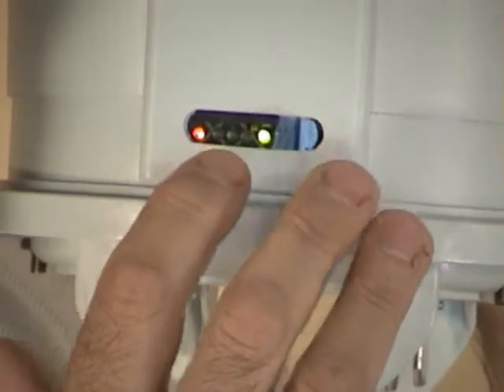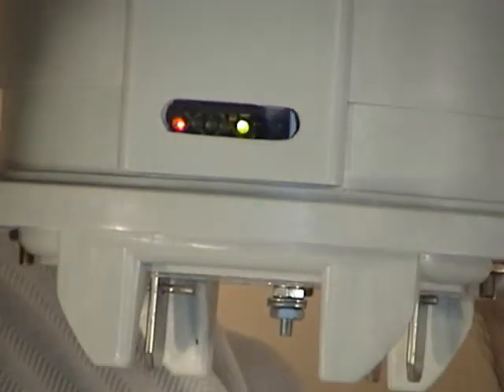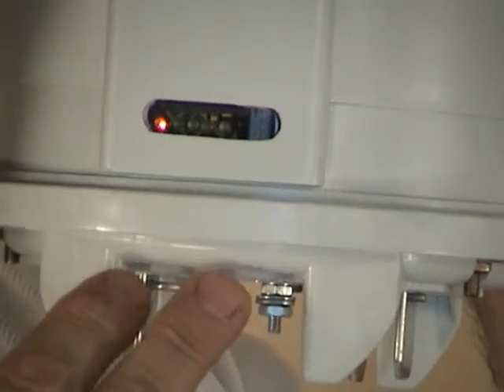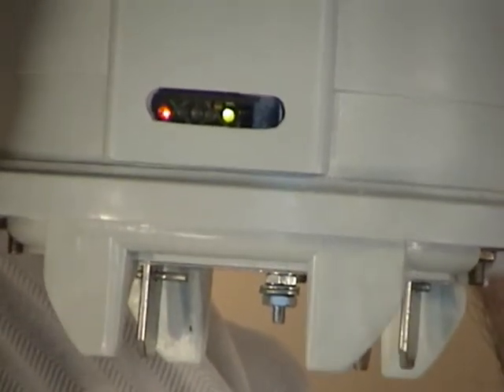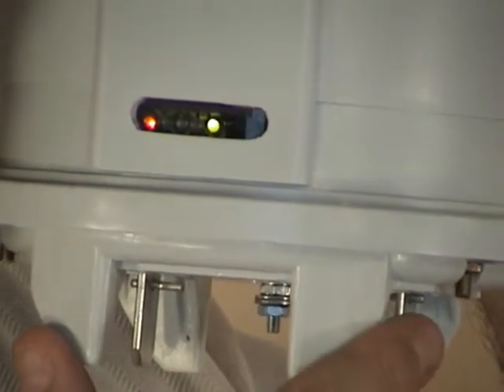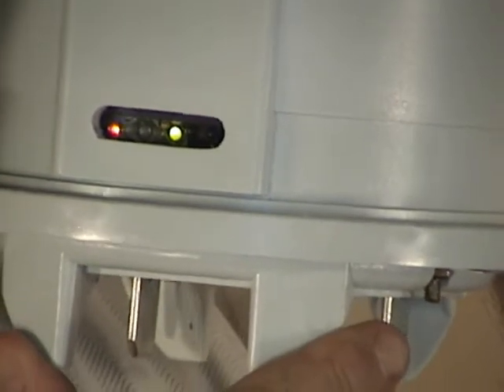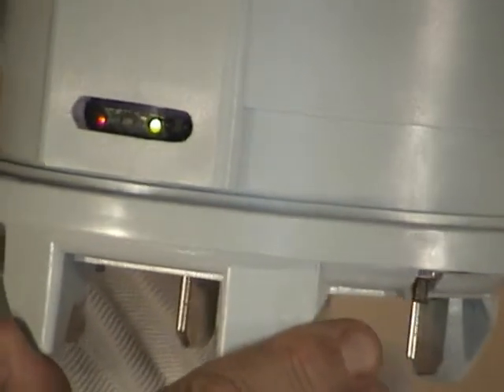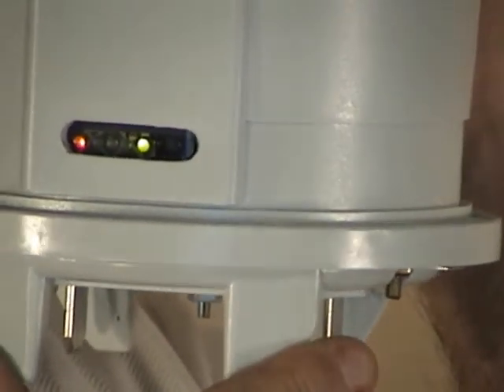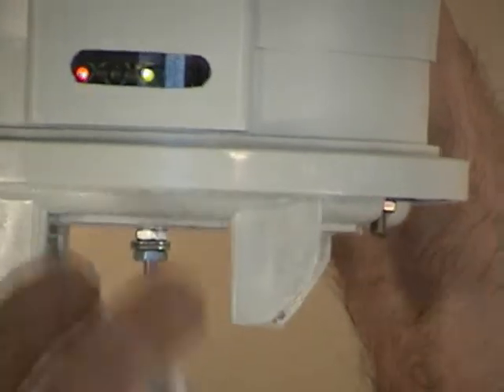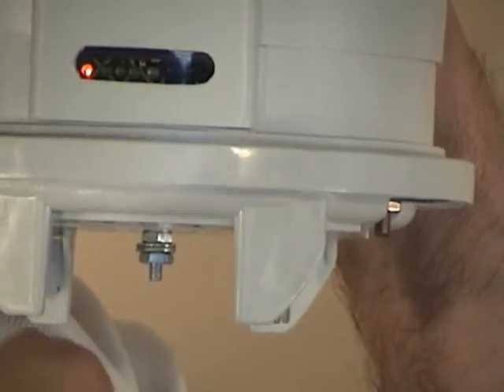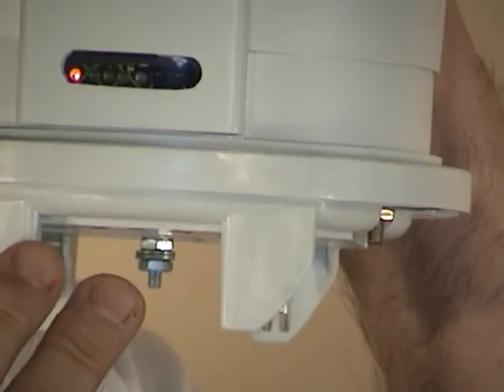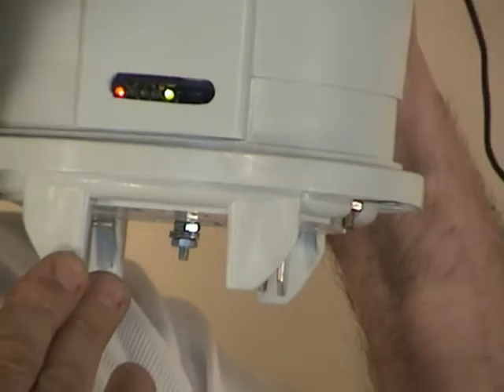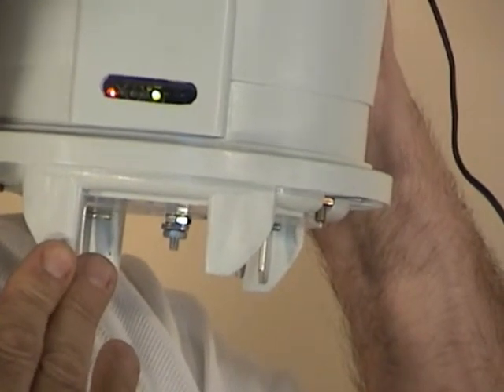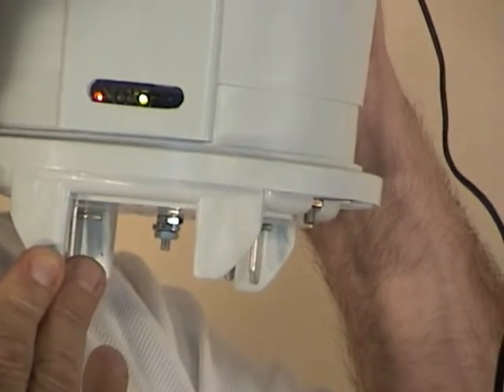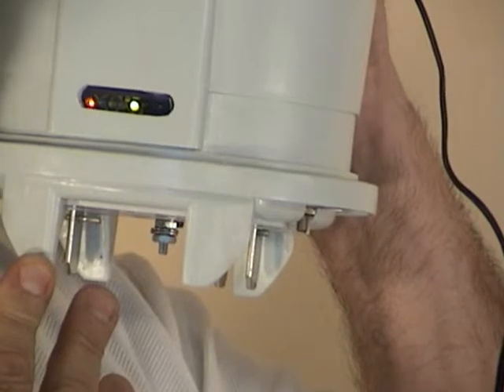They're a dual color LED, and depending on whether they're green or red, there's an intelligence about it, and there's a listing in the manual that will let you know if you see a certain type of flash, it means it's ready to record. Another type of flash will indicate other conditions. This LED array will give you conditions of various different aspects of the meter socket logger. The LED array will tell you that the unit is charging, that the unit has power between L1 and neutral. It will also tell you that the unit is recording, and it could also tell you that the unit has memory in it that has not been downloaded, or that there is memory in it but it's about to be erased because it knows that it has been downloaded.